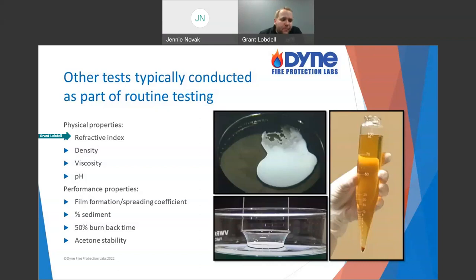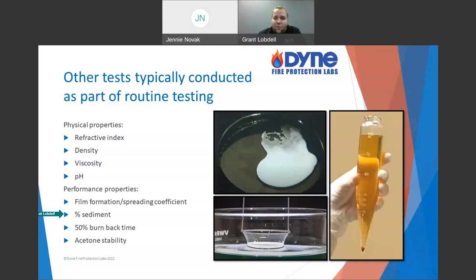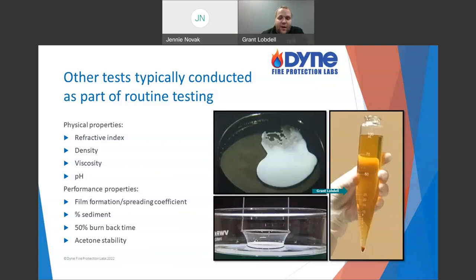Burn back and acetone stability are required by IMO specifically for protein foams. Sediment is required in all IMO samples and is something you can request for NFPA testing. For sediment testing, we take 100 milliliters of sample, put it in a centrifuge — spinning it fast causes the more massive particles to settle toward the bottom, separating out sediment that's not in solution. We quantify that as a percentage. IMO has a requirement that it be below a certain amount; NFPA doesn't require it annually, but we can do it if you're interested.